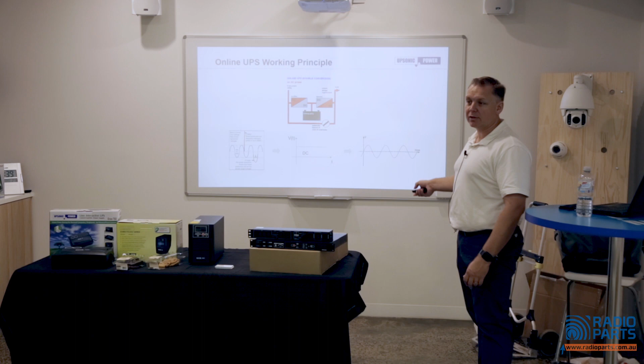It's also faster too, isn't it? Yeah, that's the other important thing. Charged and always full. Yeah, there's no break. So if the supply fails, the rectifier stops working. The inverter just gets its DC from the batteries instead of the rectifier. There's no break. Yeah. It's an instantaneous thing.